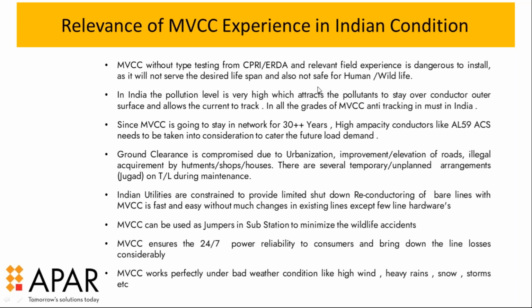As I told you, in India the pollution levels are very high, and it attracts pollutants to stay on the conductor's outer surface, which allows the current to track. So in all the grades, whether it is 11 kV, 22 kV or 33 kV, we recommend that it should be anti-track.